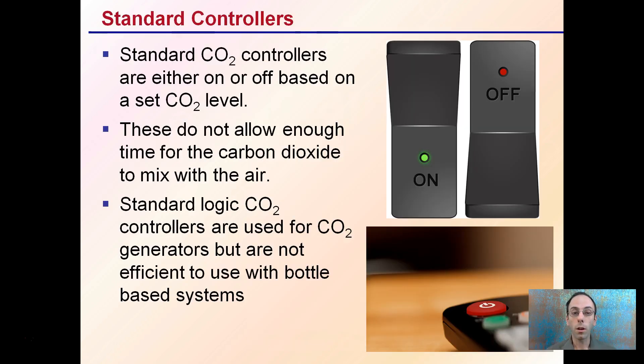First, standard controllers. Standard CO2 controllers are either on or off based on preset CO2 levels — it's like flipping a light switch on or off. These do not allow enough time for carbon dioxide to mix with the air. Standard logic CO2 controllers are used for CO2 generators but are not efficient for bottle-based systems.